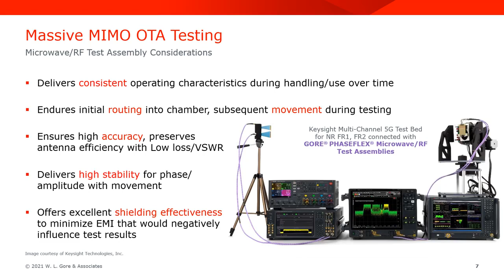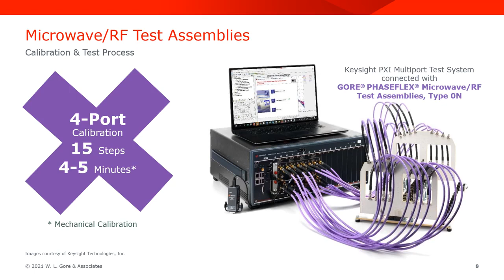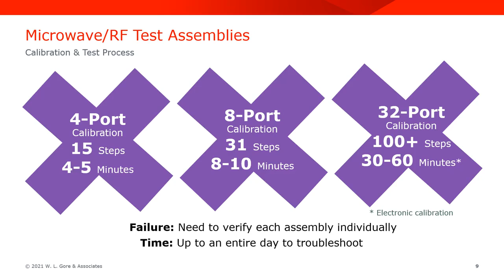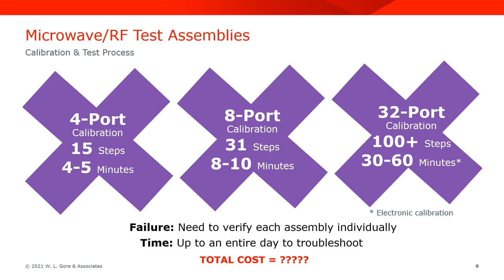To calibrate a 4-port VNA using a mechanical calibration kit, it takes about 4 to 5 minutes to complete the calibration process. To calibrate an 8-port VNA, it takes about 8 to 10 minutes. To calibrate a 32-port VNA, it takes about 30 to 60 minutes. If one cable assembly fails, then you need to recalibrate the entire system multiple times to locate that failed cable assembly. The associated cost would be huge.